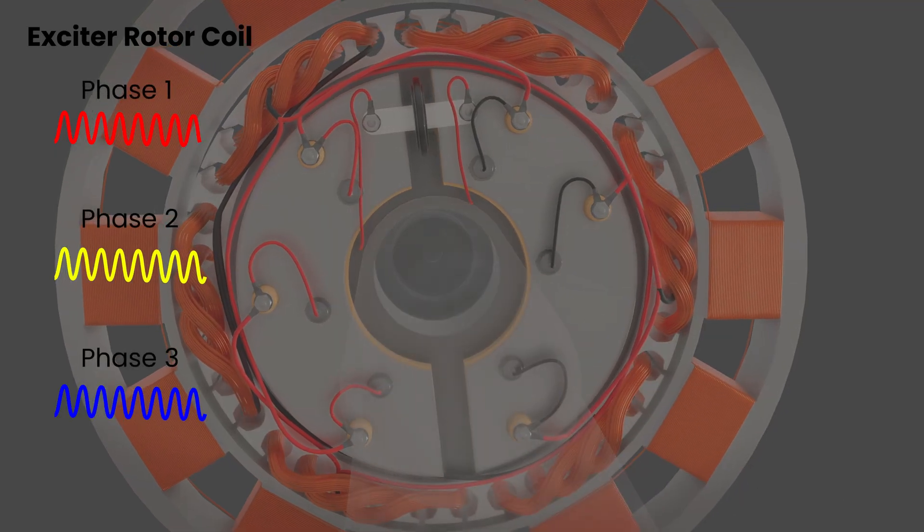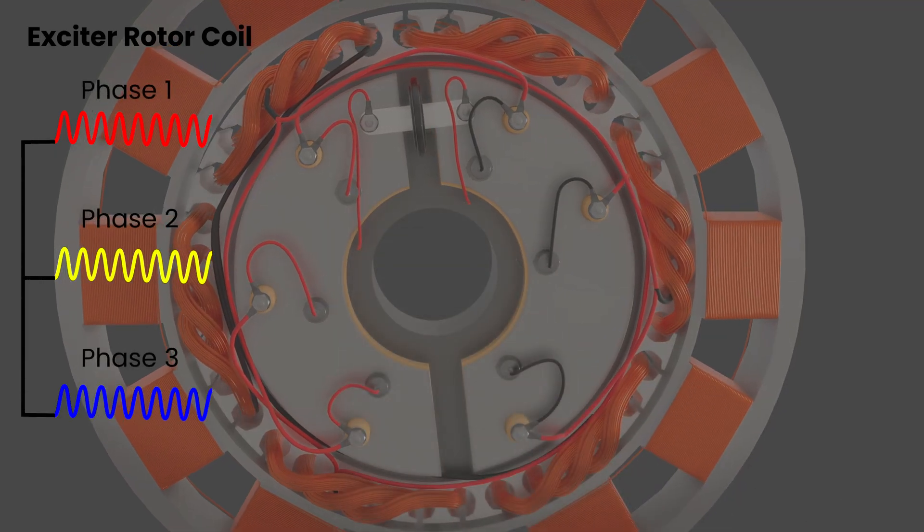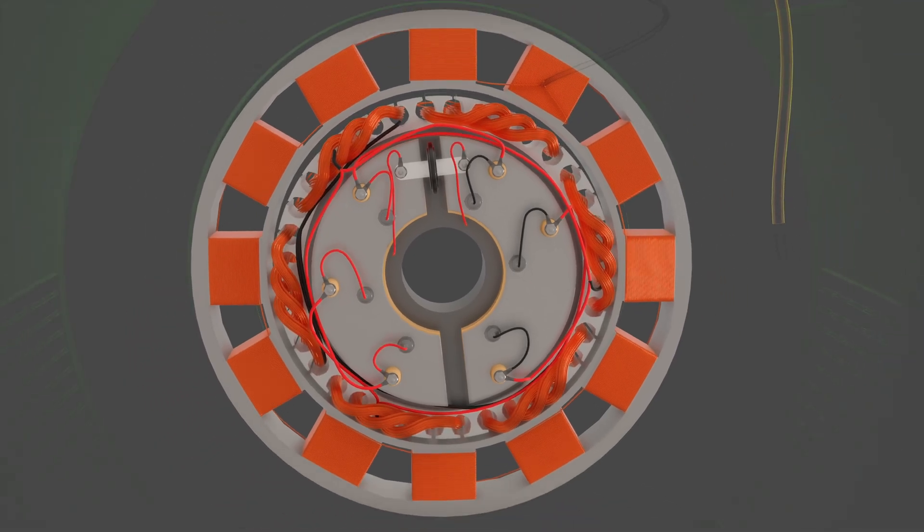One end of the three-phase exciter coils are connected in star configuration, neutral point, and the other ends are connected to the rectifier bridge. Each phase connects to the junction point between a positive and negative diode pair.